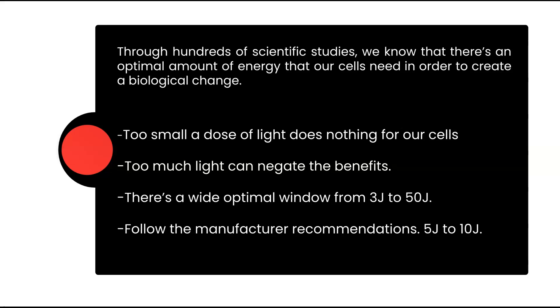There's a wide optimal window, anywhere from 3 joules to 50 joules. So, as long as you're following somewhat closely to the manufacturer recommendation, you'll be just fine. Generally, they will recommend you use 5 to 10 joules.